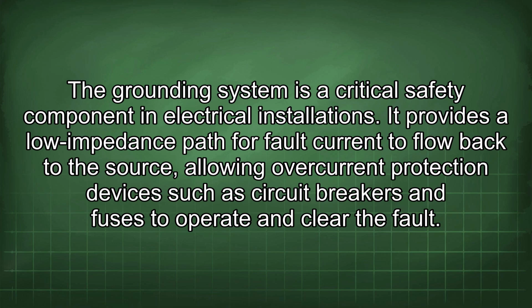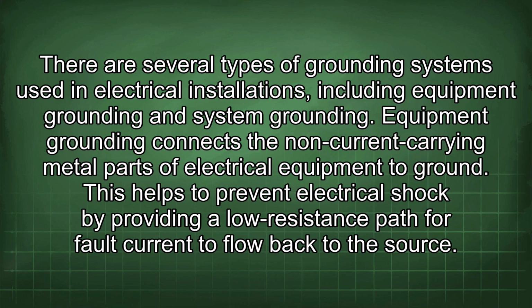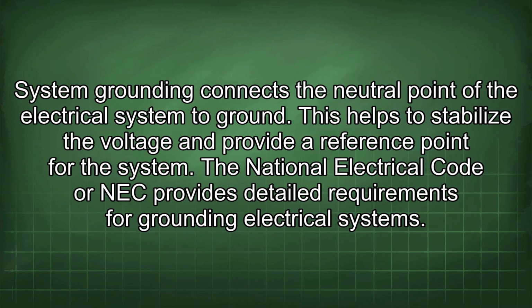The grounding system is a critical safety component in electrical installations. It provides a low impedance path for fault current to flow back to the source, allowing overcurrent protection devices such as circuit breakers and fuses to operate and clear the fault. There are several types of grounding systems used in electrical installations, including equipment grounding and system grounding. Equipment grounding connects the non-current carrying metal parts of electrical equipment to ground. This helps to prevent electrical shock by providing a low resistance path for fault current to flow back to the source. System grounding connects the neutral point of the electrical system to ground. This helps to stabilize the voltage and provide a reference point for the system. The National Electrical Code or NEC provides detailed requirements for grounding electrical systems.